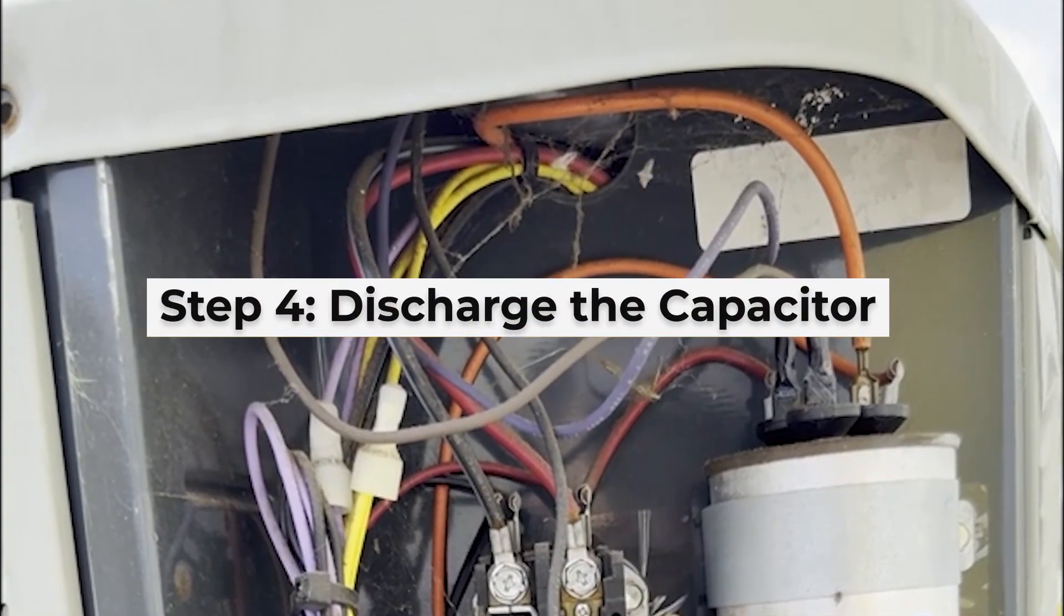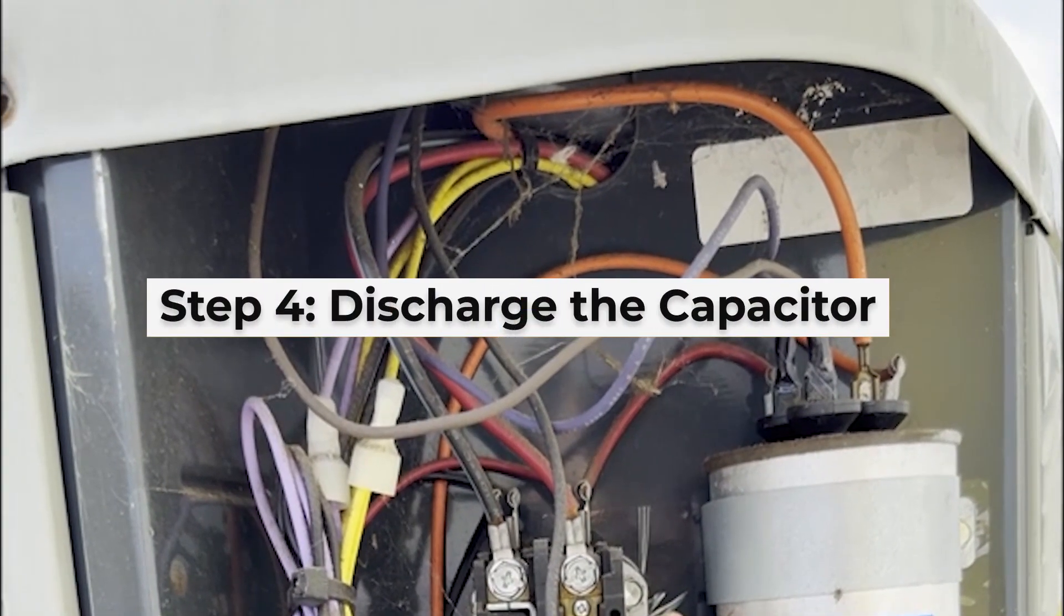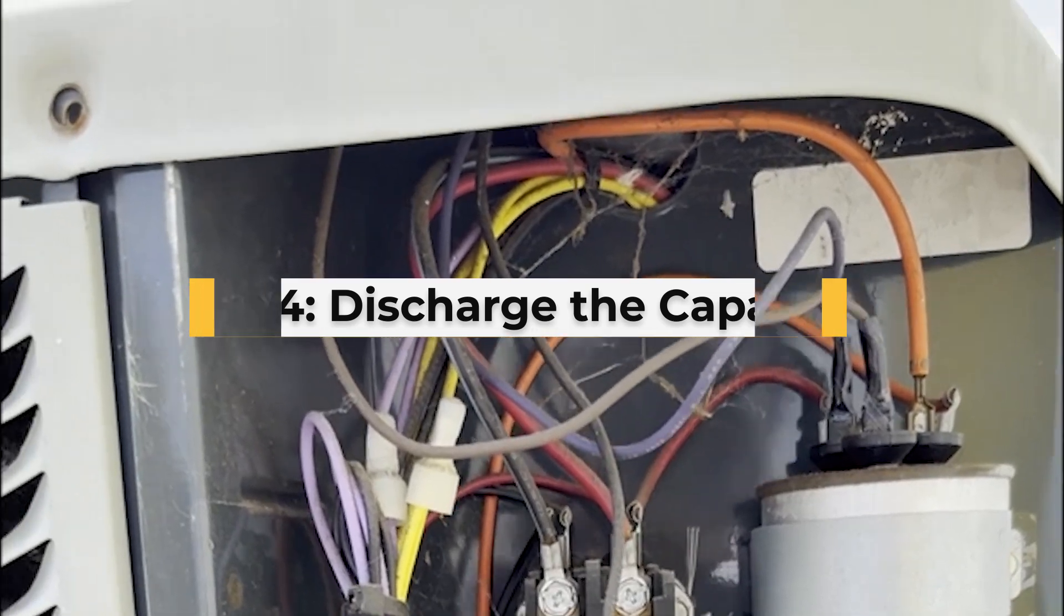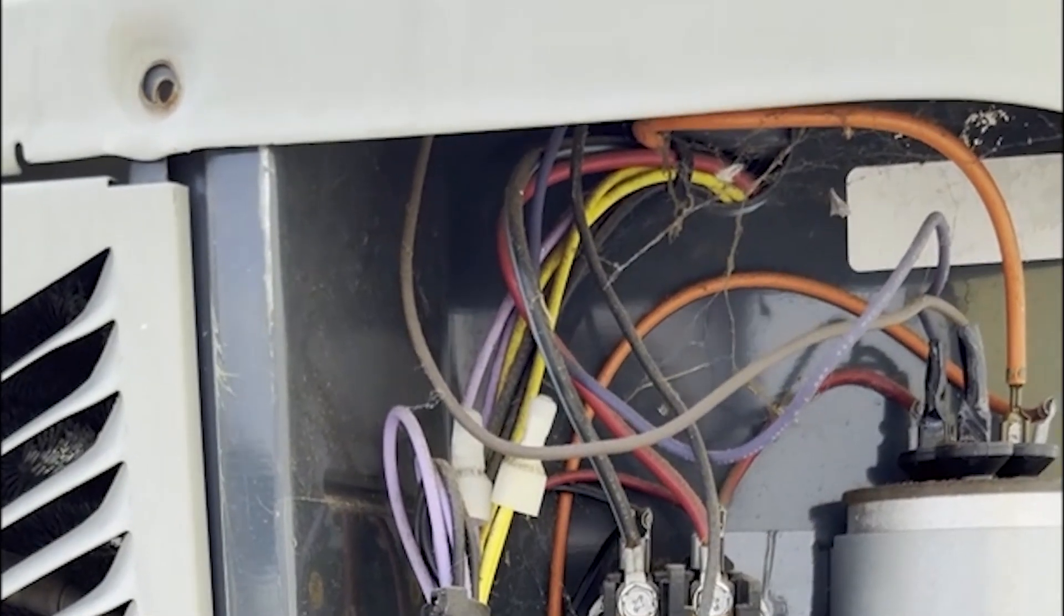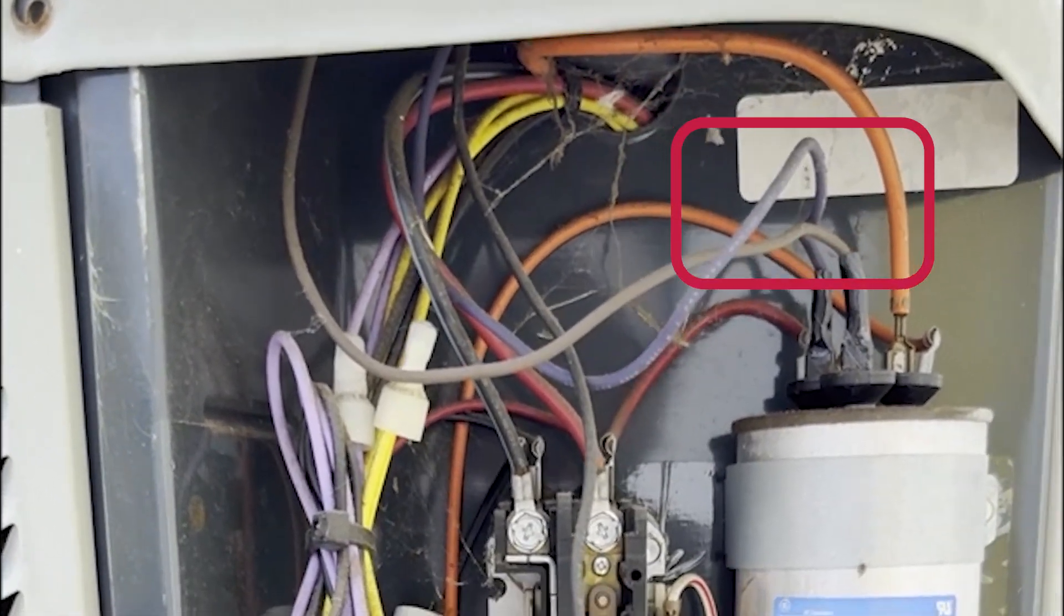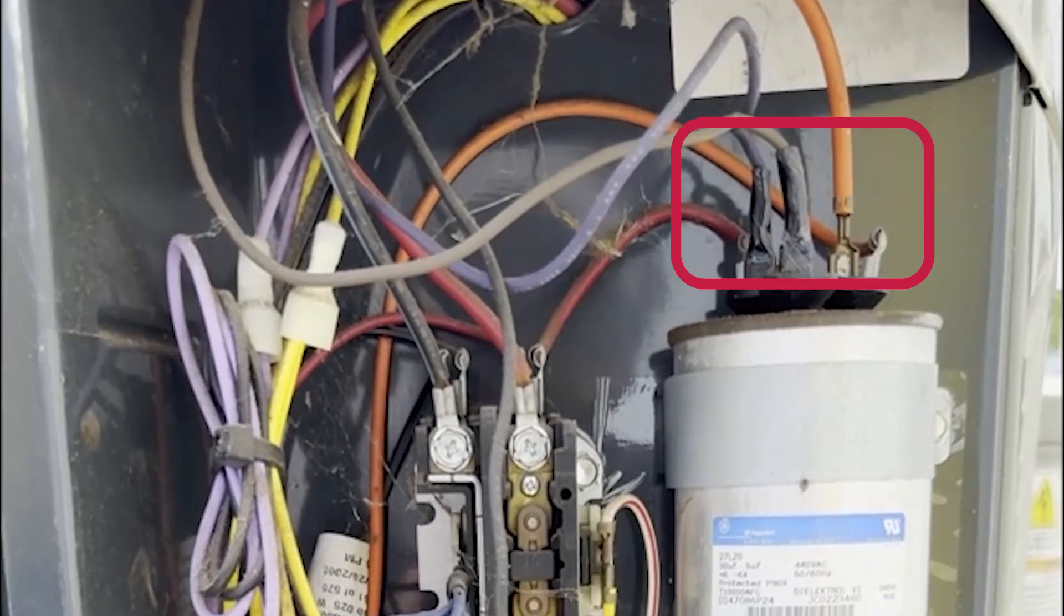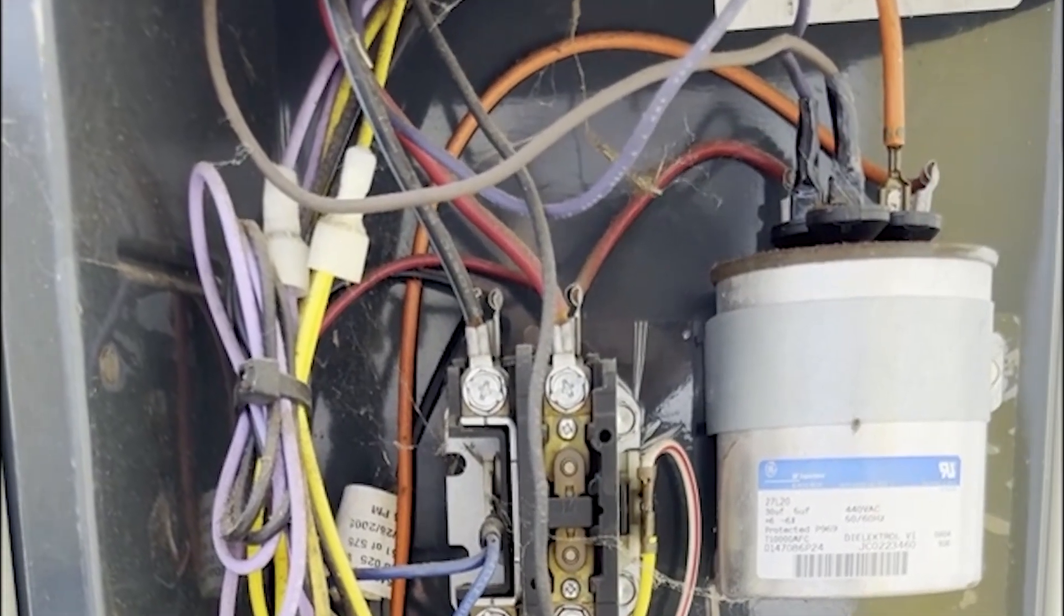Step 4: Discharge the capacitor. Although rare, capacitors can hold a charge. To be safe, take an insulated screwdriver and short the terminals by touching common to fan and common to hermetic. Just a quick tap between each pair is enough.